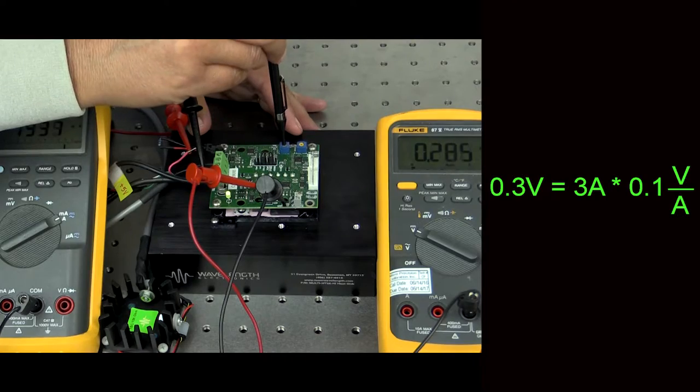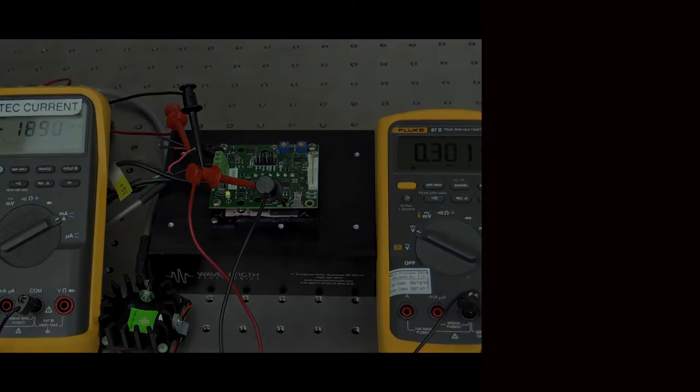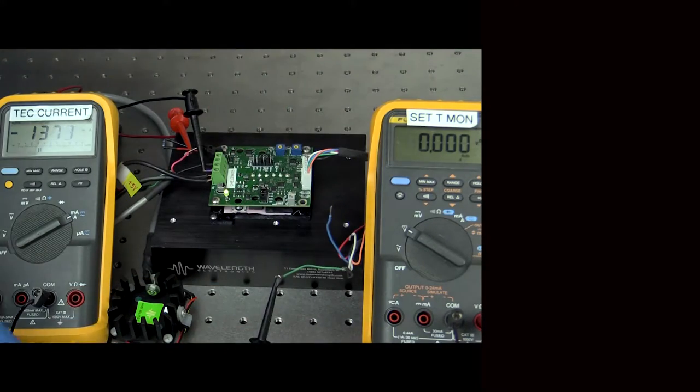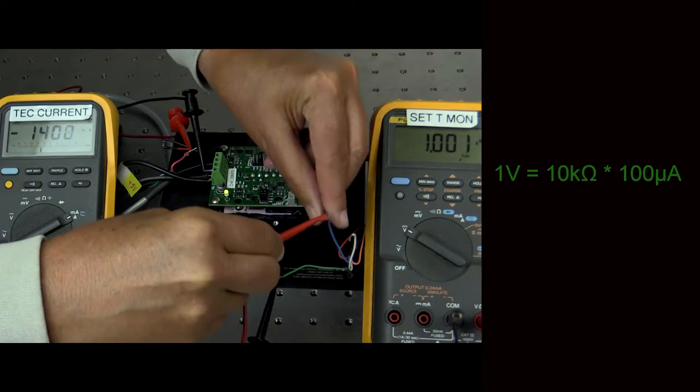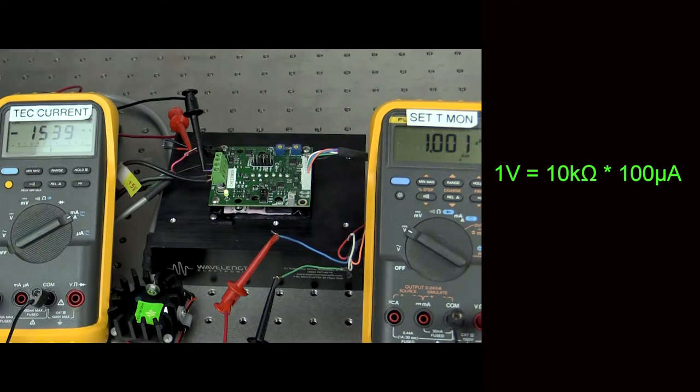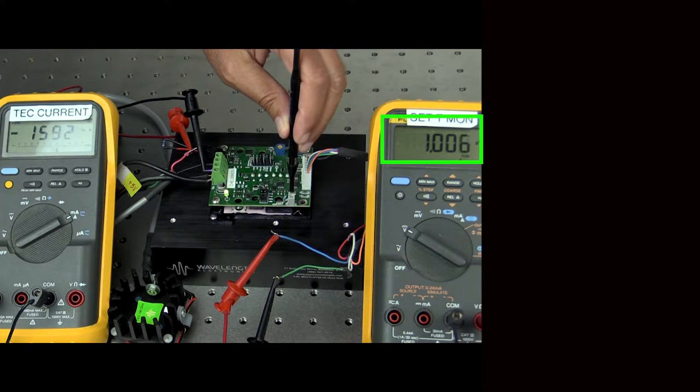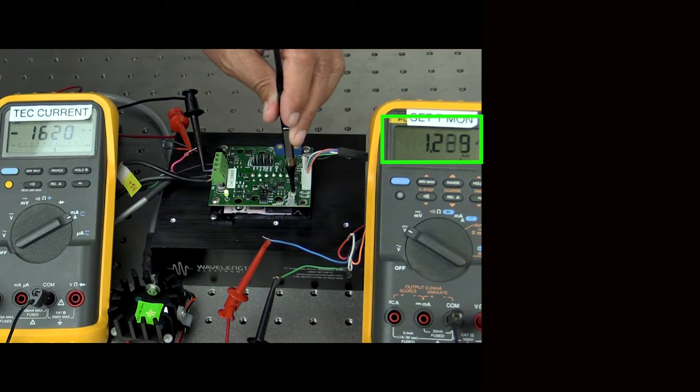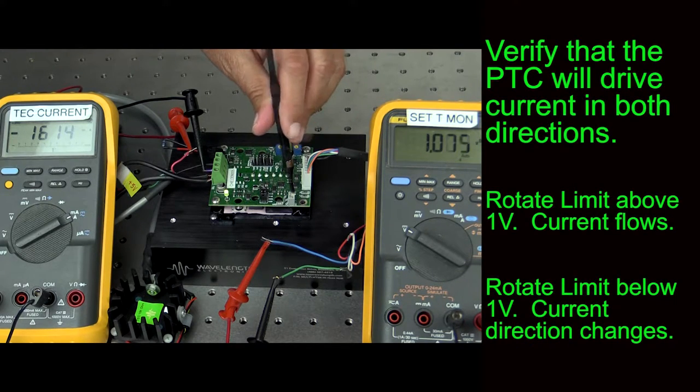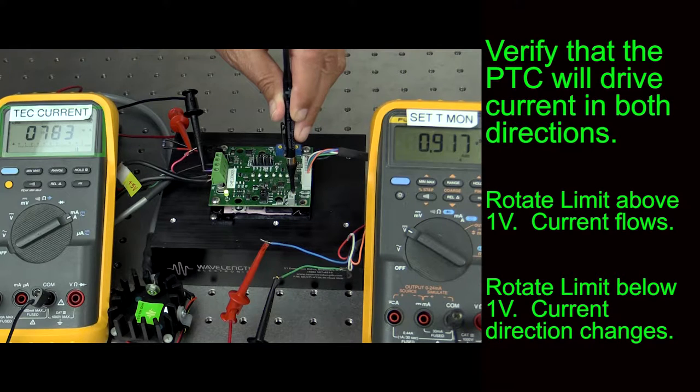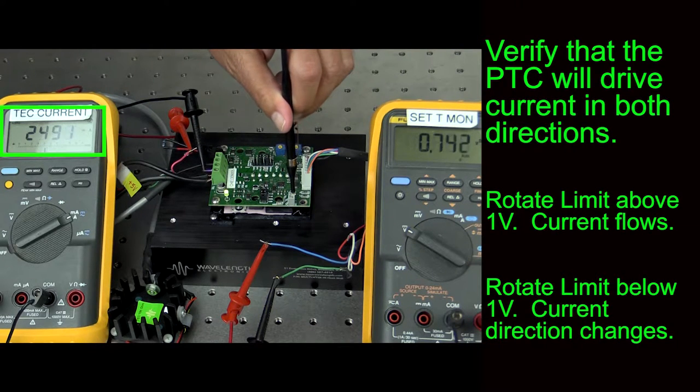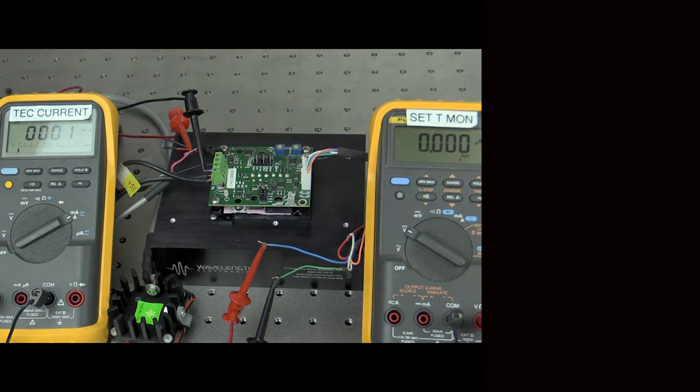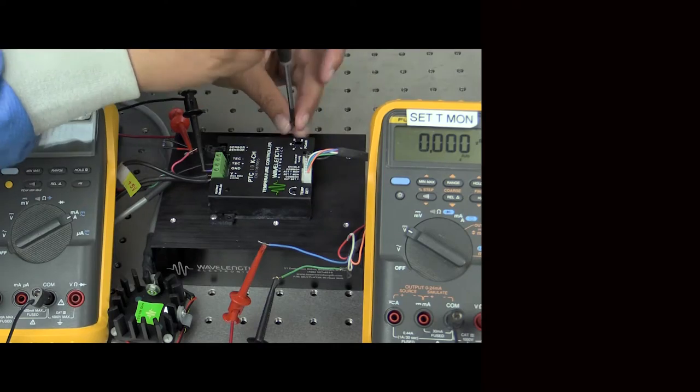Now we can rotate the limit current trim pot until the voltmeter reads 0.3 volts. Set up another voltmeter to monitor the setpoint across pins 4 and 5 of J3. The 10k ohm of the resistor times the 100 microamp bias current will produce a 1 volt signal at the sensor input. Rotate the setpoint trim pot so it goes above 1 volt. Now rotate the setpoint trim pot so the voltage is below 1 volt. The current direction changes. The sign on the current changes. Now you know the controller can drive current in both directions. You can turn off the power supply now and replace the cover.